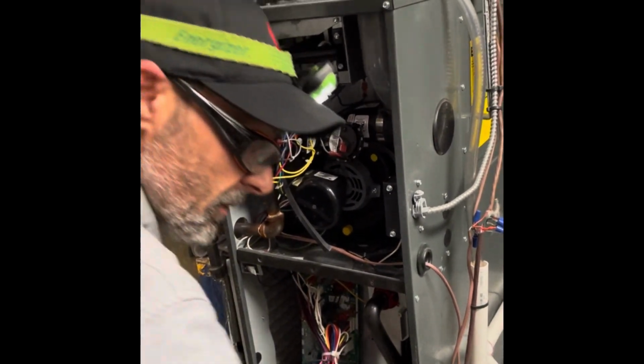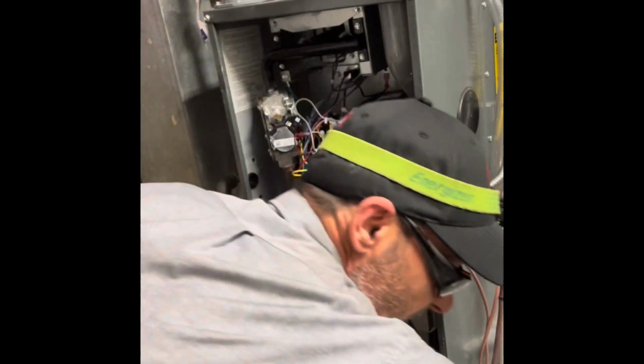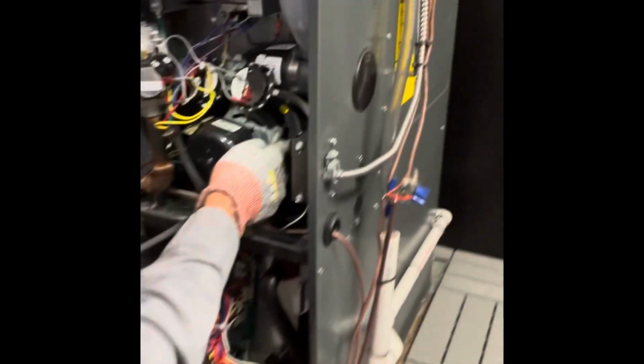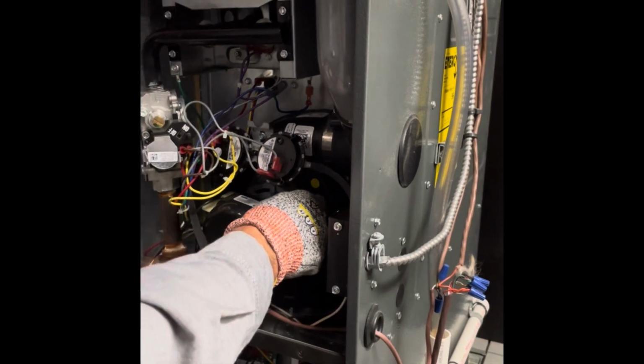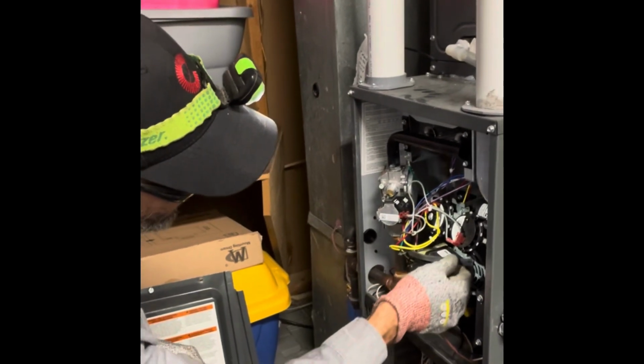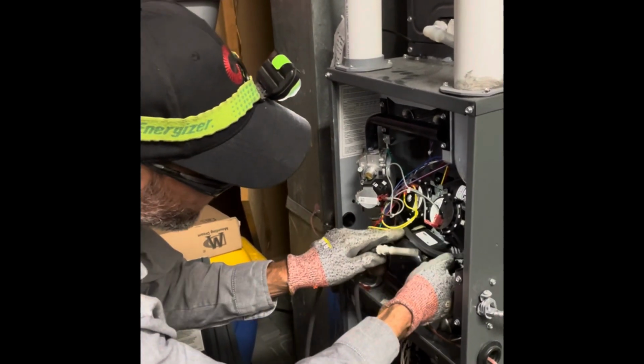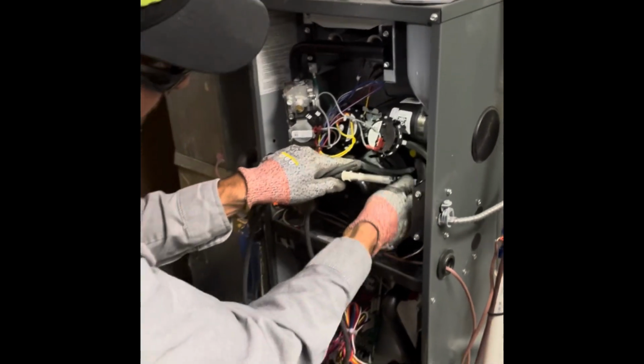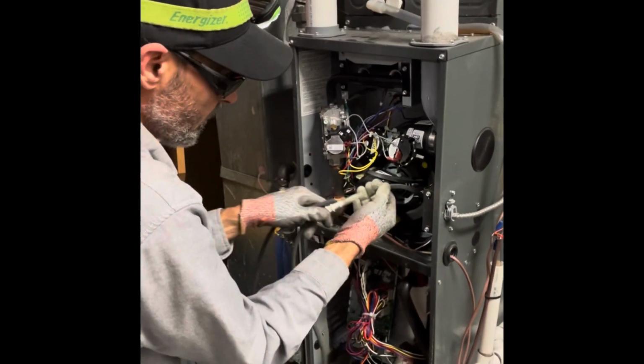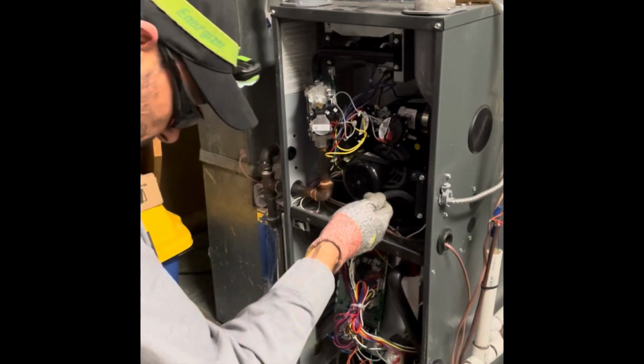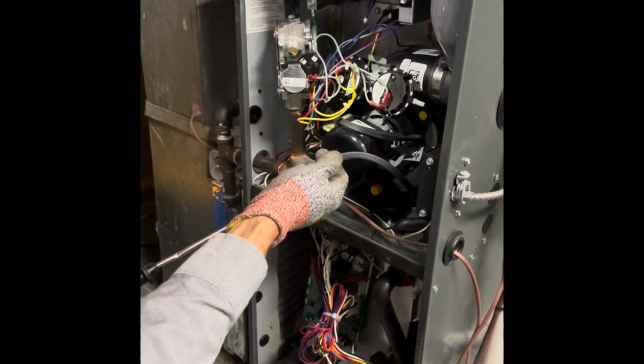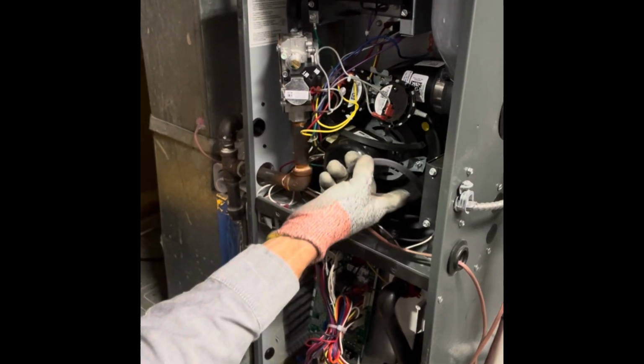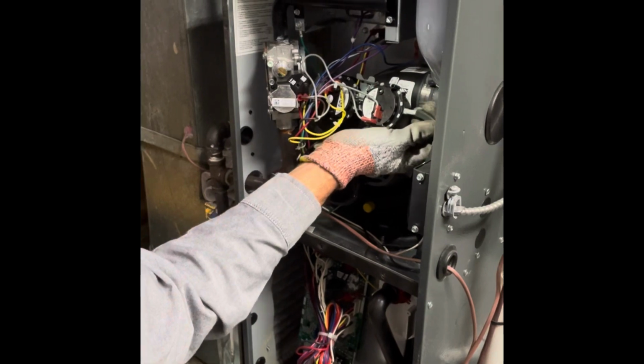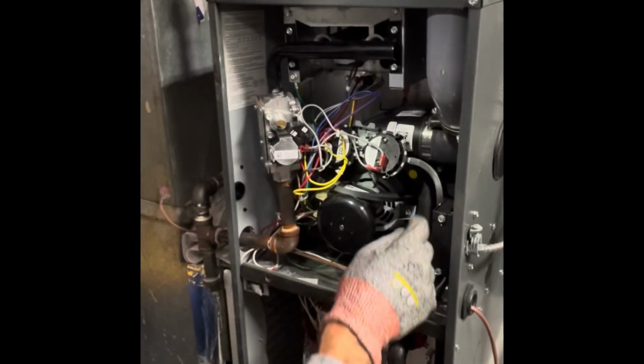And I have some adapter hoses that I'm going to hook up to in order to confirm that these lines are cleared. So first one will be right here. So that's clear. I will not blow any air in that hose because it is hooked up to our pressure switch and I do not want to damage the switch. I'm going to remove this other little tube. I've got a little probe here, so I'll blow some air in this hose. Again, I'm not going to undo it from the end and blow this way because I can damage our pressure switch if I blow air in there.